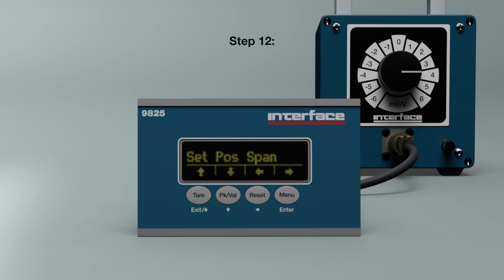Step 12. Press the menu key to scroll right to the next menu item called Set Negative Span. Press the peak and valley key to begin setting the negative span. Fixture will be displayed. Make sure the load simulator is set to output 0 millivolt per volt, then press the menu key to set the fixture value. A dashed line will migrate across the display as the 9825 records the input.